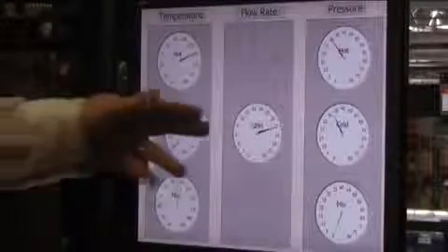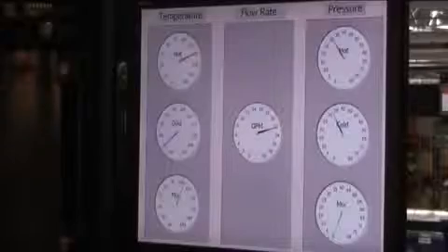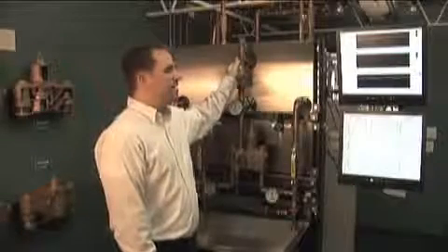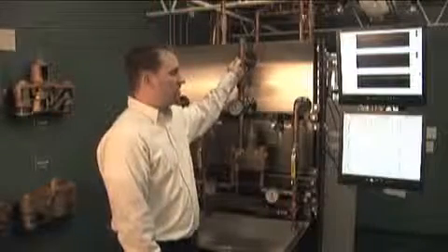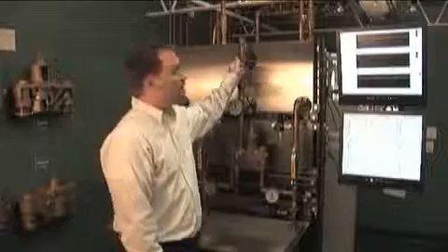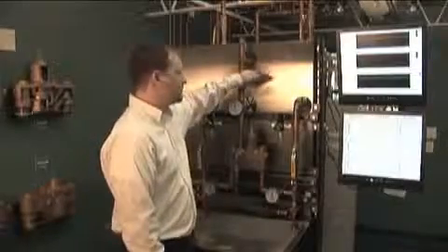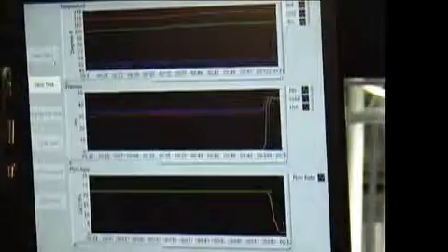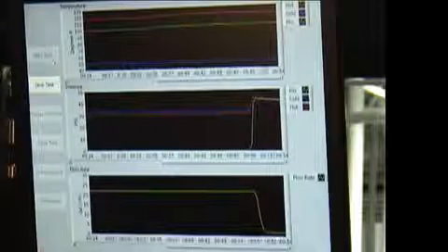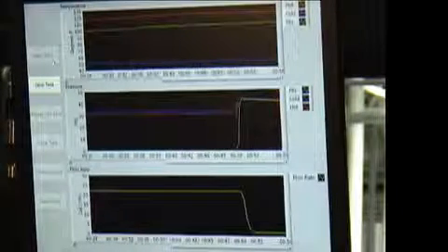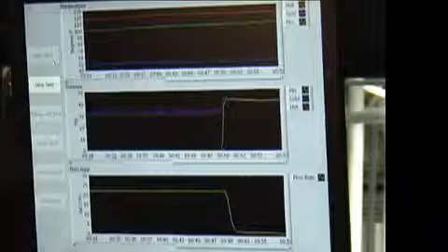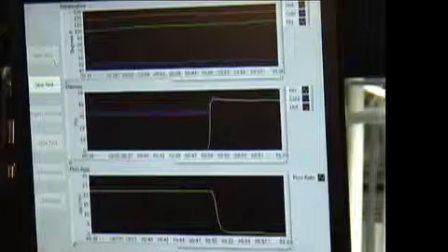So we're flowing steady at 22 gallons a minute at a very steady temperature, as you can see, going across the top there. This is a high demand situation if we're looking at 22 gallons a minute, but how well does the valve respond to low demand? I'll reduce the flow down to a gallon or two a minute, and you can see that my temperature is still held steady across the top.